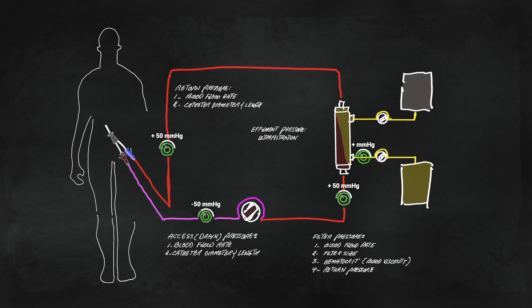Effluent pressure sensor, which sits between the membrane and dialysate flowing out, is a function of UF rate prescribed and membrane flux characteristics.